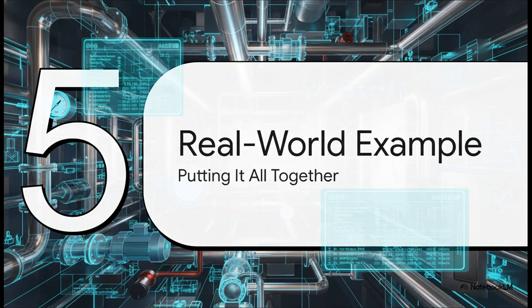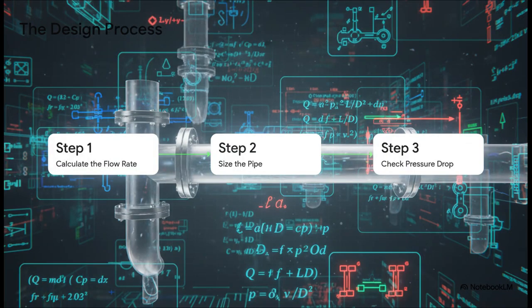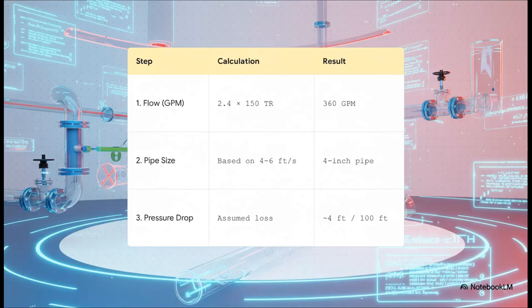All right, enough with the theory. Let's put all these pieces together and walk through a quick, real-world example to see how an engineer actually makes the final call. When you break it down, it's really just a simple 3-step dance that every MEP engineer follows. First, you calculate your flow rate. Second, you pick a pipe size based on your target velocity. And third, you double-check to make sure the pressure drop for that pipe size is right where you want it to be. Let's see it in action.